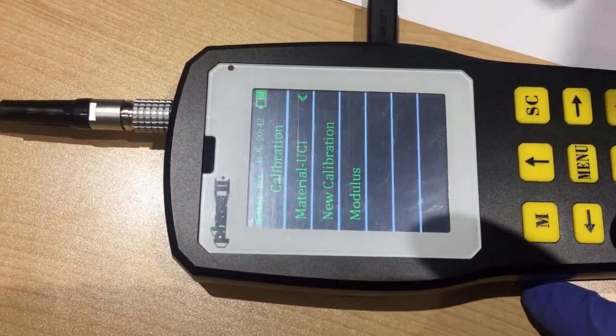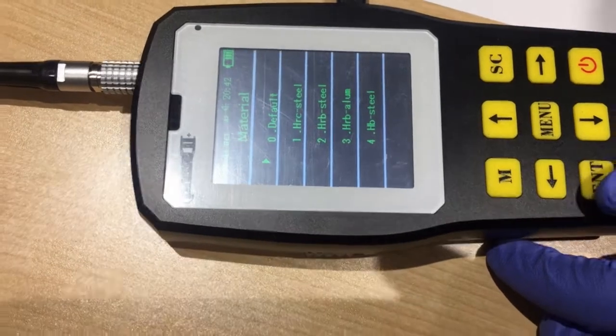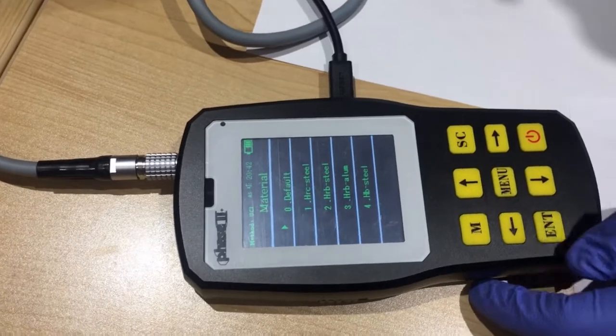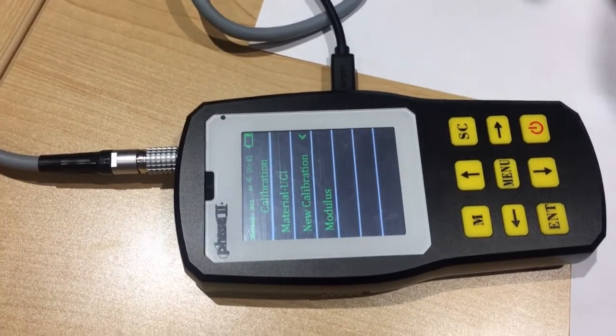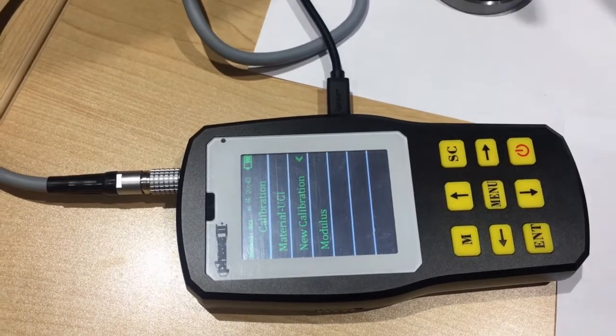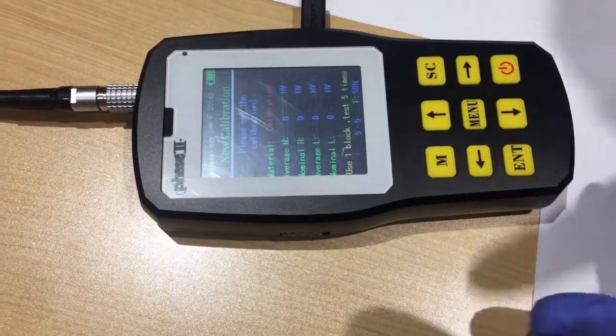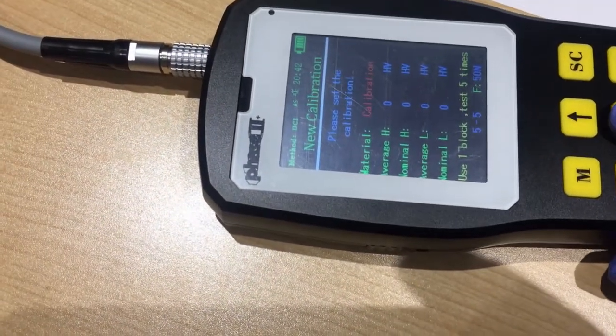Firstly, you need to choose your material, UCI, which depends on the test block you want to use. And also, you can set a new calibration. You can name it yourself as you want. That's an easy way for you to personalize your machine.